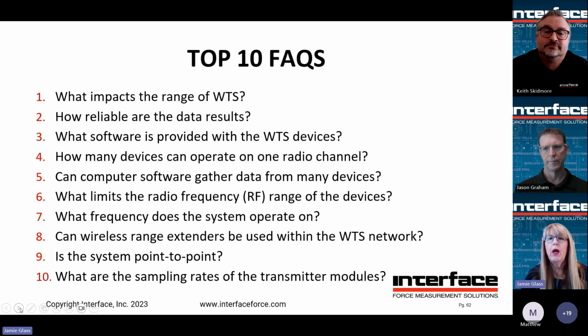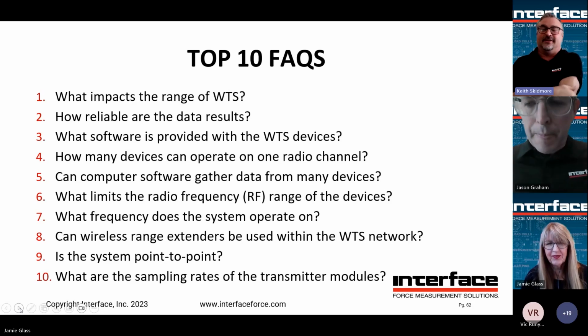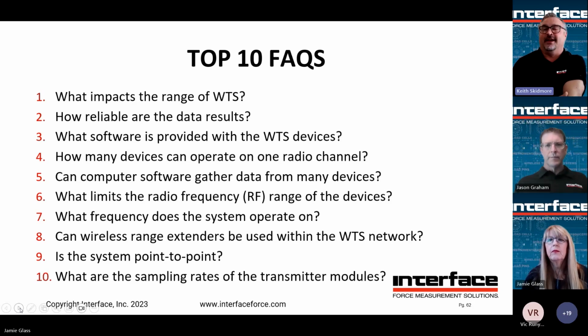Justin asked whether the transmitters buffer data on board with any averaging. Yes, good question. The A to D rate is fixed at 200 samples per second. One of the parameters you set using the toolkit is how many readings it takes. If you set it in milliseconds, 5 equals 1 reading. So it takes 1 reading from the A to D, then the A to D stops. It doesn't run all the time, but when it's running it's always 200 samples per second. So you can say take 3 readings, which is 15 milliseconds.